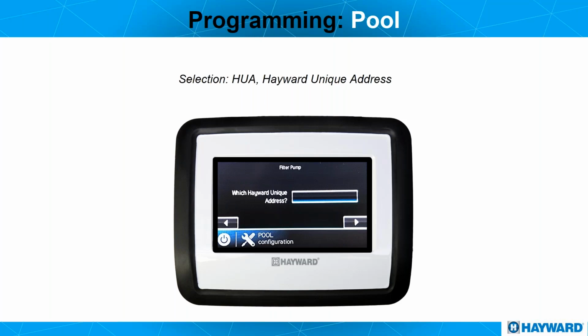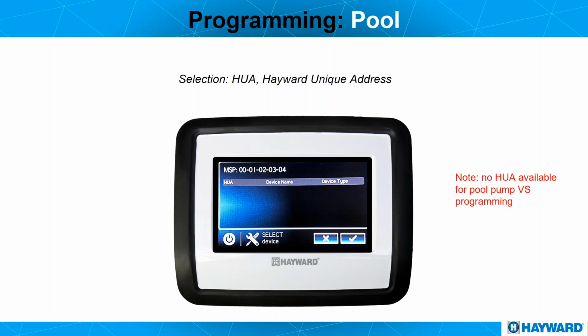First of all, the system needs to know the HUA, the Hayward Unique Address. We click on the empty box and we can select something - take note here, you see that there's no device available. Why? Because the pump is not connected.